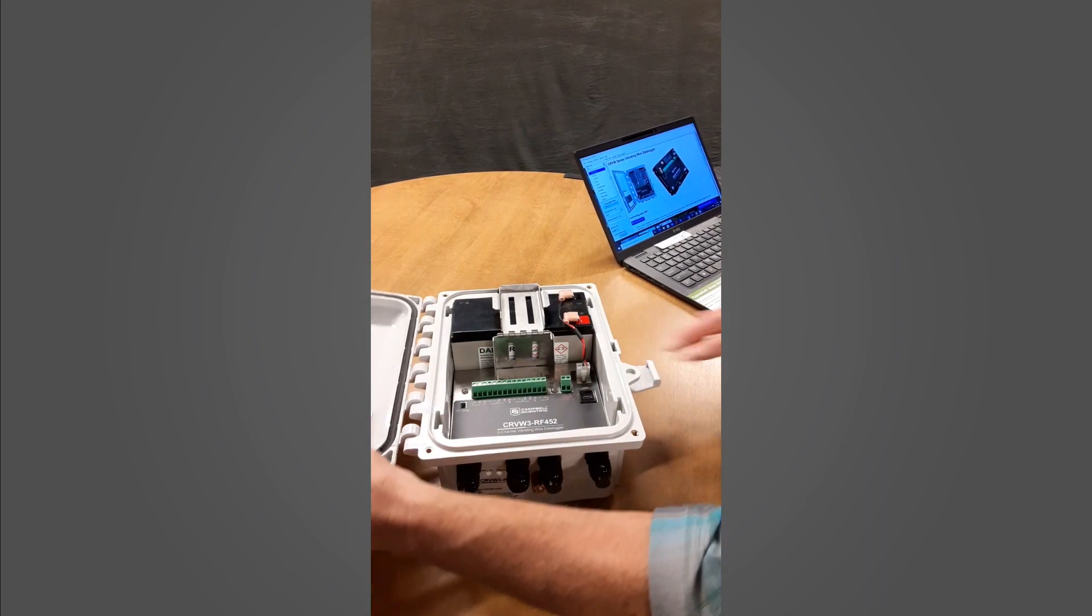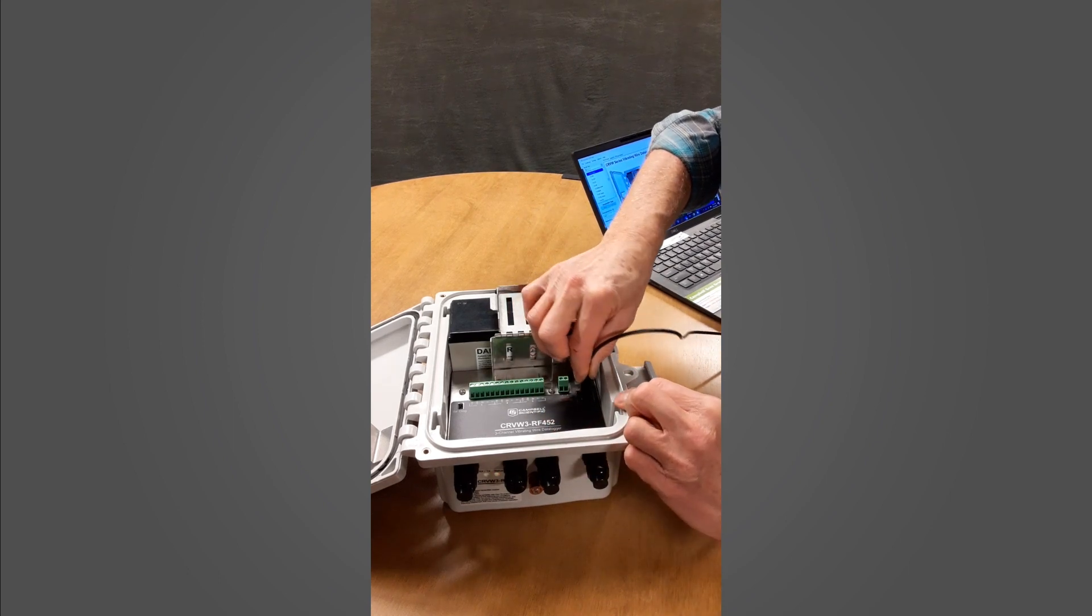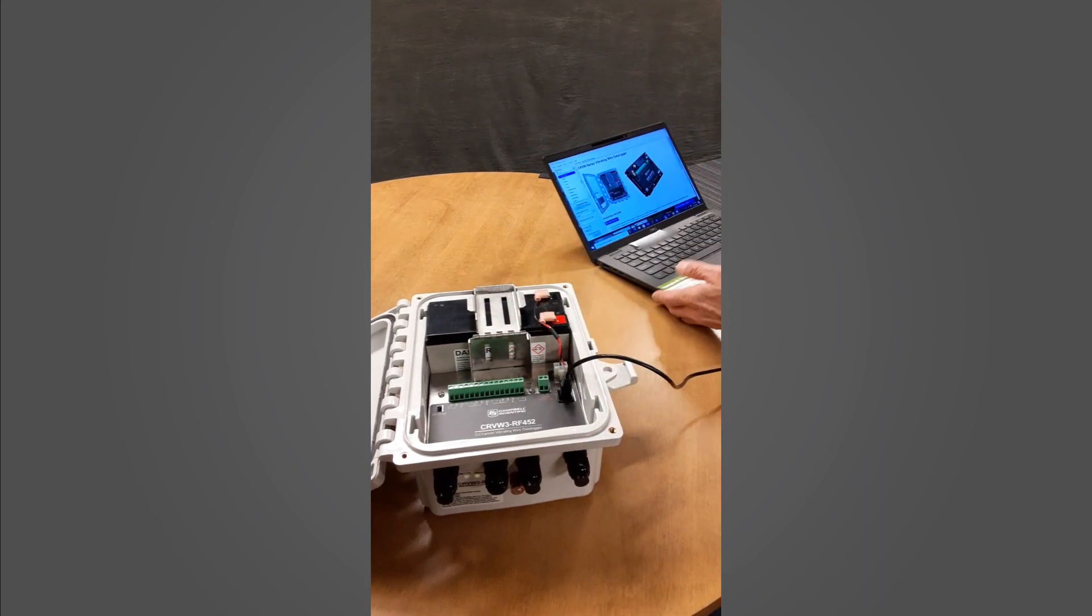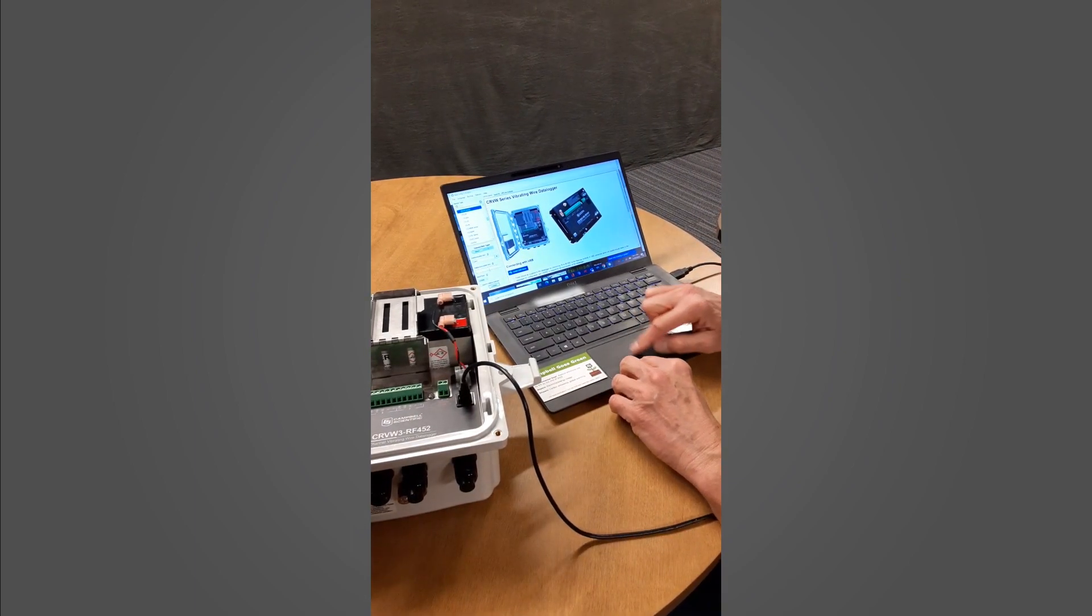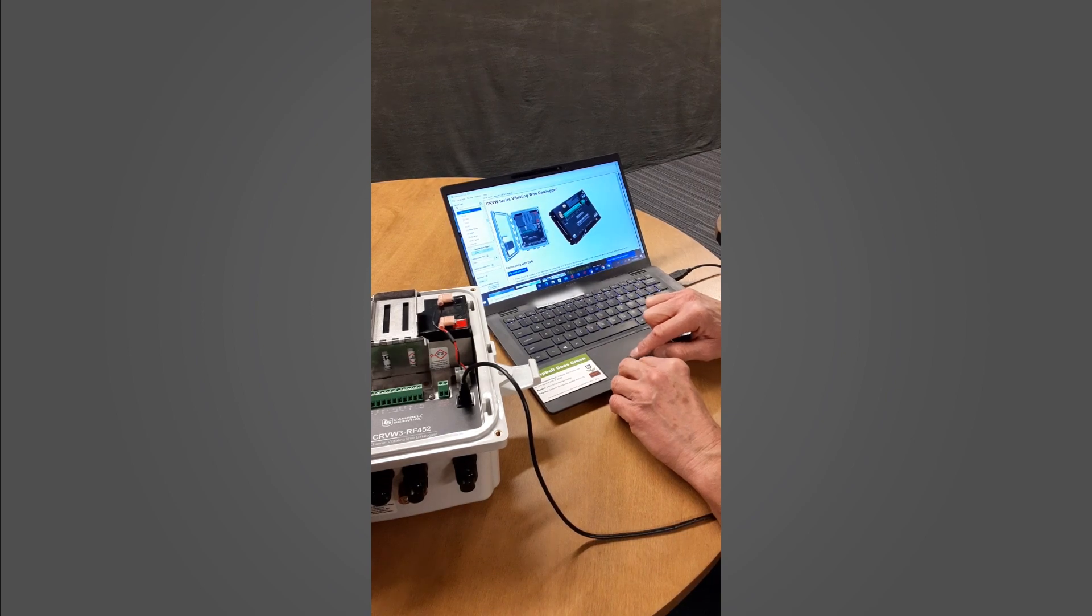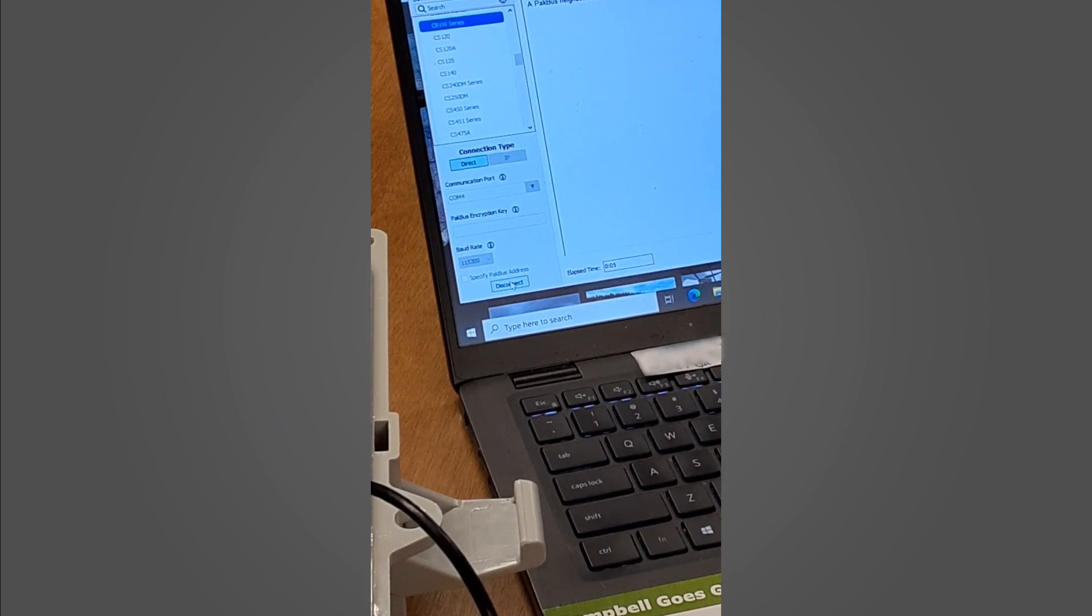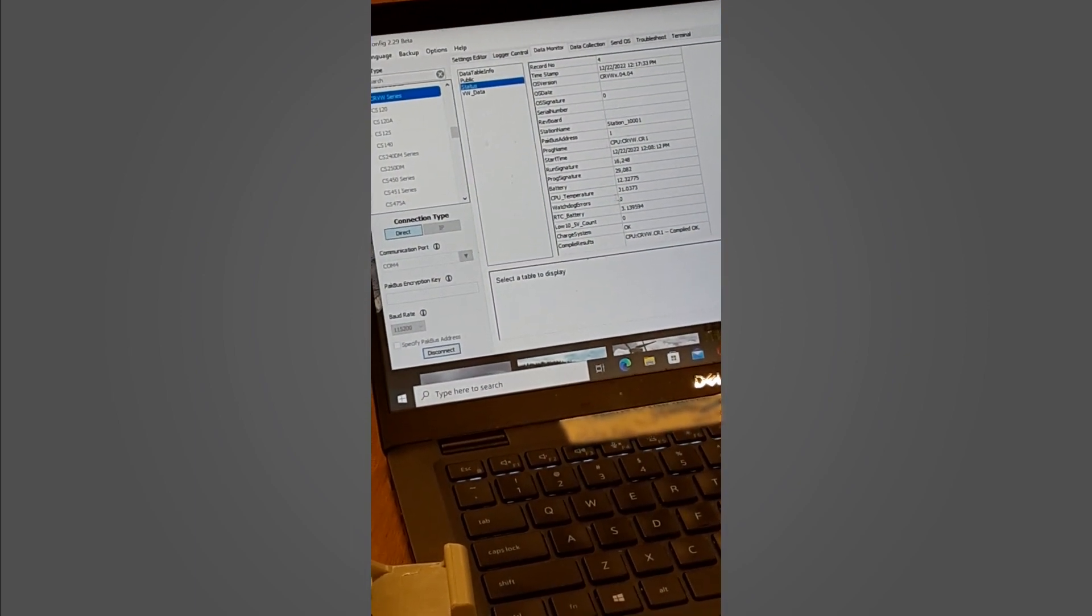We'll show you how to check your lithium battery. We're using our device configuration software, selecting the COM port and connecting. Once it has found the CRVW3 and pulled up the information, in the data monitor we look at the status table for the RTC battery right here.